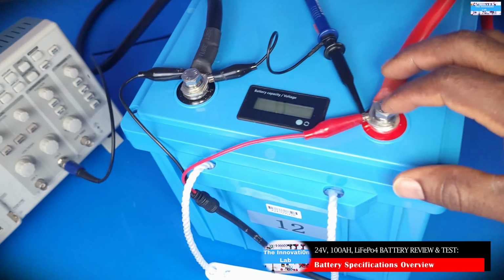For the load test, given that what we have here is essentially a complete system, the battery, the power inverter, and the charger, the plan is to connect the battery system to the power inverter and then apply a load of close to 1,000 watts on the power inverter, and that way we're going to use that load to discharge the accumulated energy in the battery system.